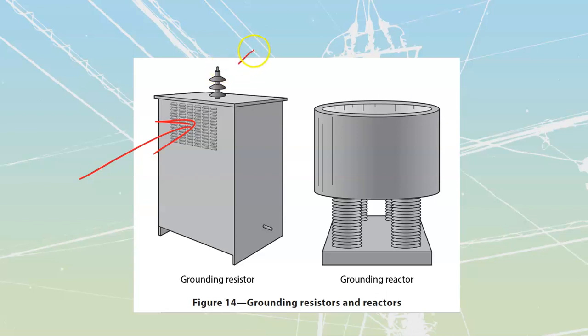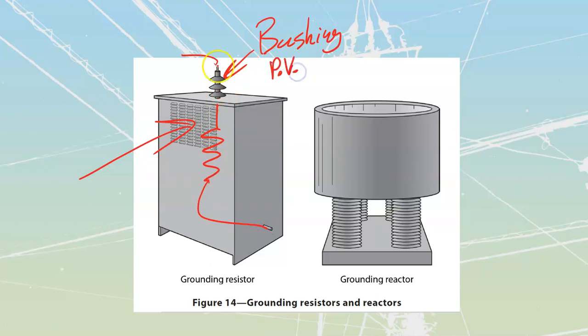Secondly, we're going to have this bushing out of the top here. That bushing is where we're going to have our high voltage connection. Remember that during a fault, my actual resistor, made up of many small ones, gets all the way up to phase voltage, so it needs a high voltage bushing because we use these on high voltage systems.